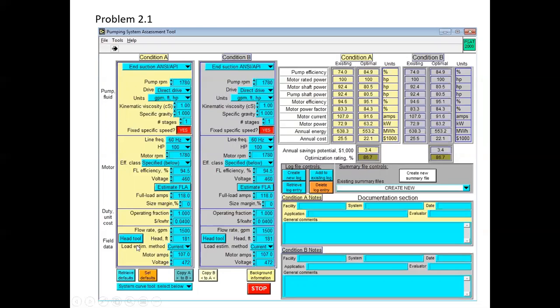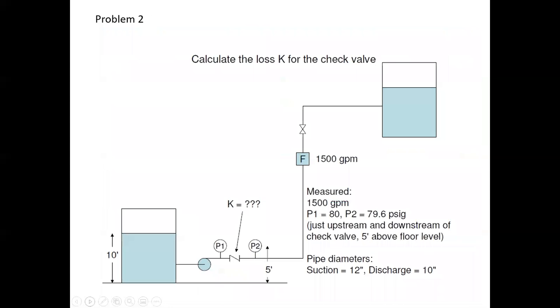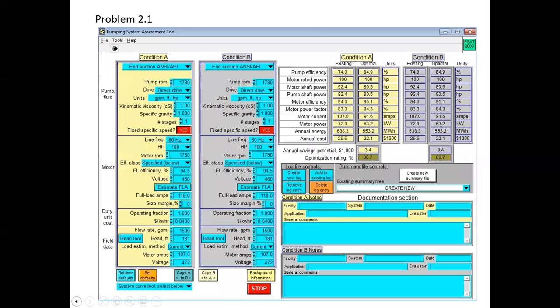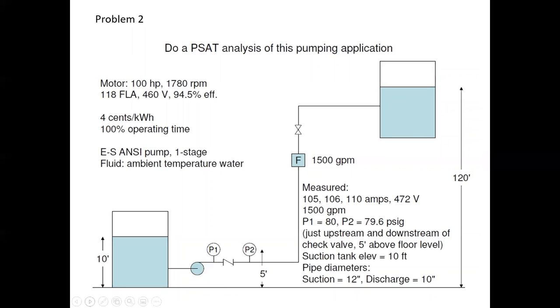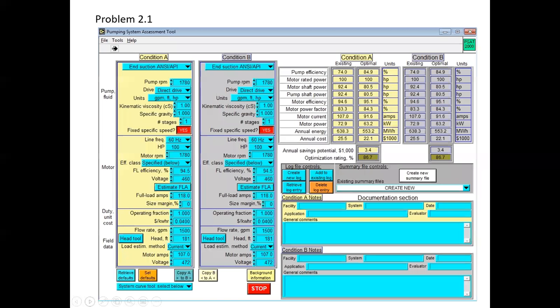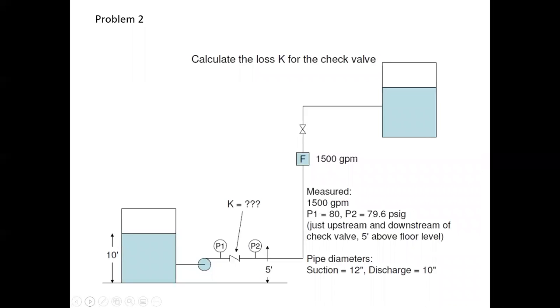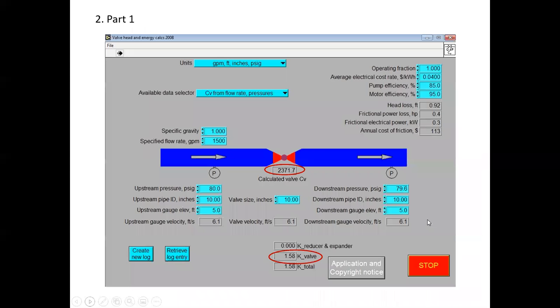Okay, so we've done the PSAT analysis. Now let's go see. The first thing we just said is, do a PSAT analysis. So, okay, we've done that. I didn't really ask any questions about it. Then it says calculate the loss coefficient K for the check valve. Okay, so there's two ways we can do this with a hand calculation, because we have a delta P. It's losing 4/10 of a PSIG. And so we've got a simple equation for that, or we can use the valve tool, which is what I've done because I'm lazy.